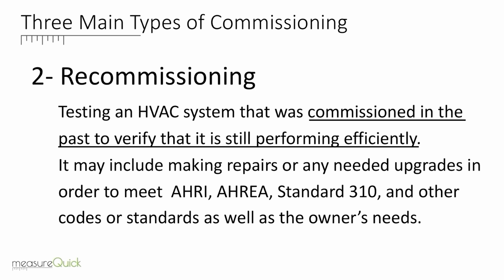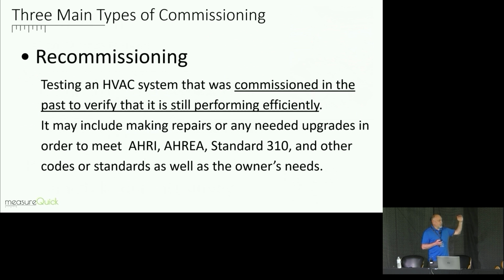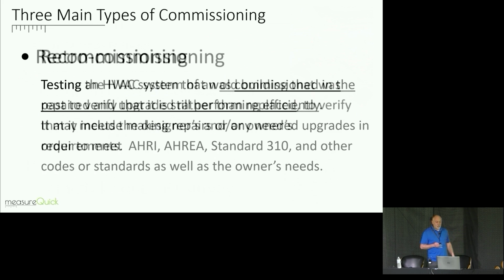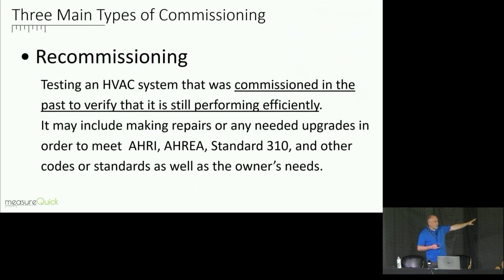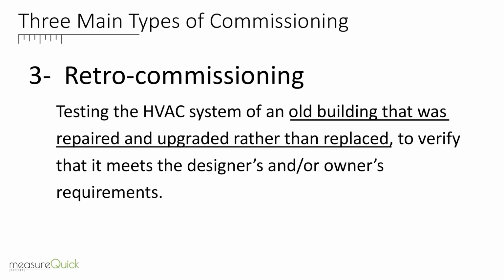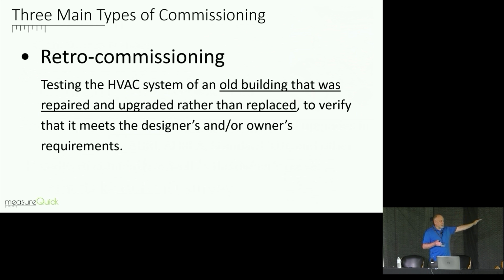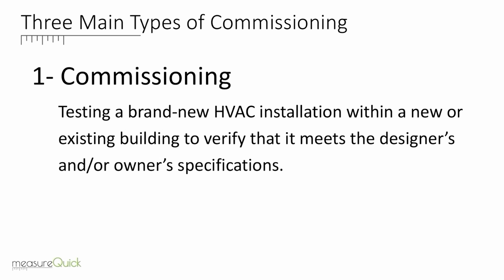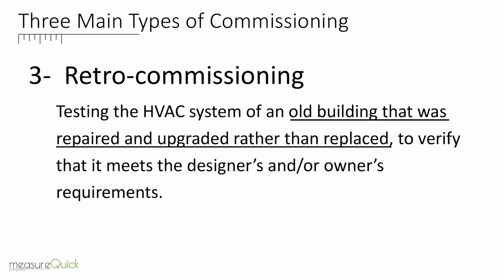Retro-commissioning is commissioning to the past design. In other words, the designer set up the spec, and we're just going to go back through it. Maybe we'll do a cleaning of it, clean the coils, clean the condenser, clean the evaporator, and then we'll retro-commission the system. And then you'll hear also recommission. That's recommissioning. And then we'll talk about retro-commissioning. Retro-commissioning is like when you get in a school system, they've torn down the walls, they've re-engineered everything, they've moved runs around, they moved thermostats, and now we're taking an old building up to a new standard, right? So those are the three you're going to hear: commissioning, recommissioning, and retro-commissioning.